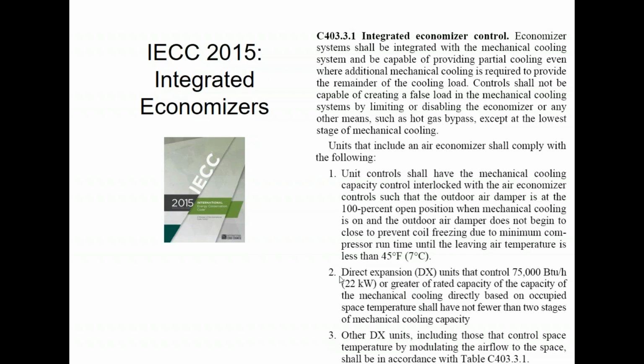Additionally, an integrated economizer is required by code. So what that means is you have to be able to run the compression in conjunction with the economizer. Because if I'm going to make you take air that's between 55 and 70, it's not going to get the cooling done all on its own. So it's going to need assistance from the compression.